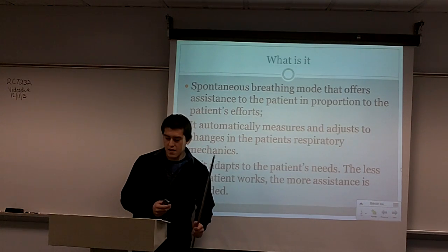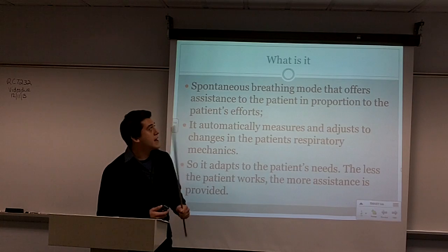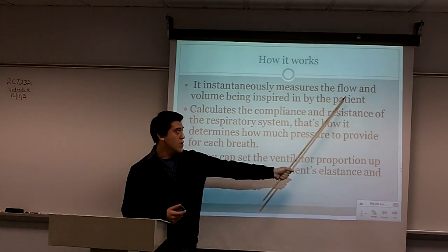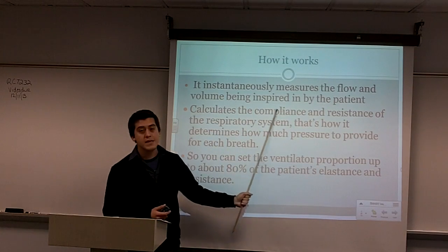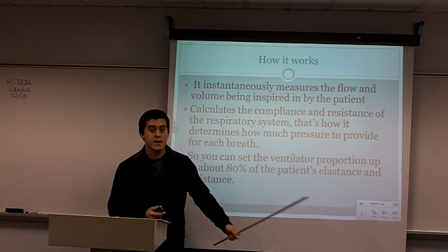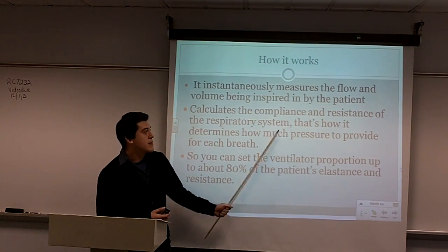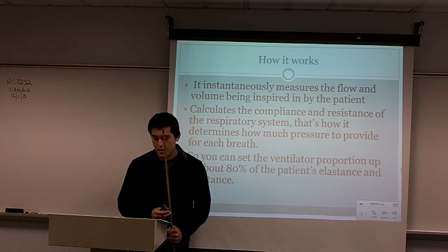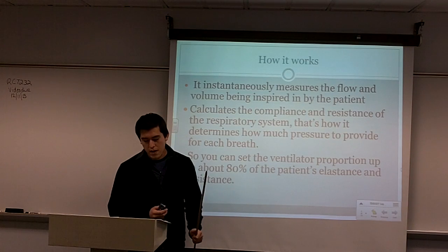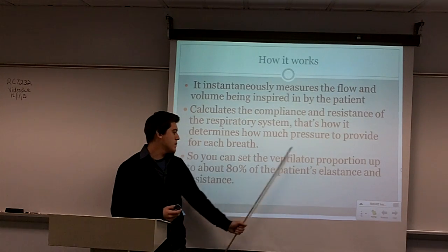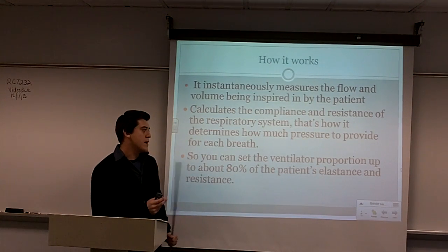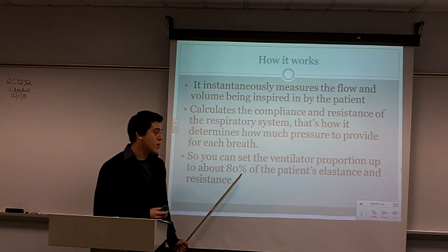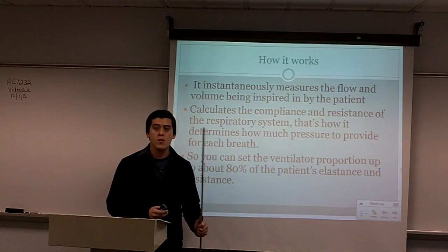How does it work? Excellent question. Well, it instantaneously measures the flow and volume being inspired by the patient. It does this by calculating the compliance and the resistance of the respiratory system. So you can set the ventilator proportion up to about 80% of the patient's elastance and resistance, meaning the machine will do 80% of the work while the patient only does 20%.